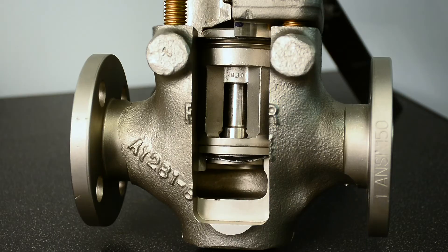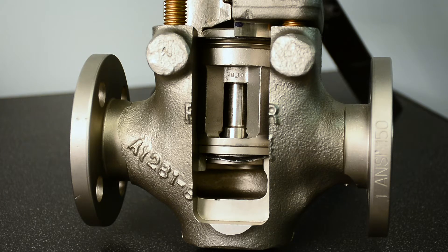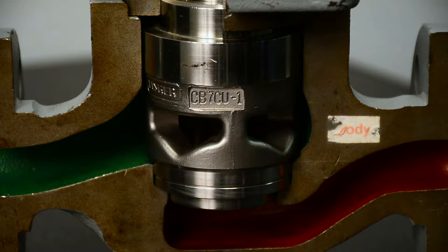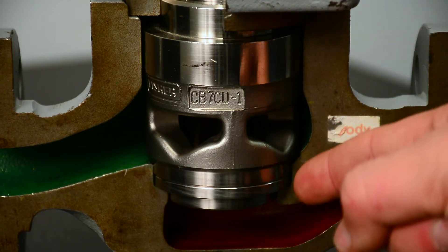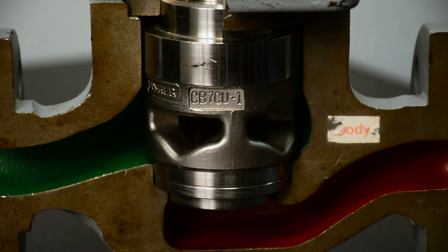Tip 5: Valve trim also requires infrequent maintenance. For critical processes, you should visually inspect the trim and replace elastomer trim components and metal seats on a yearly basis. For other applications, you can extend that out further or replace trim on an as-needed basis.